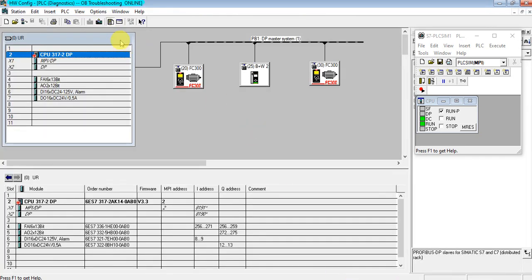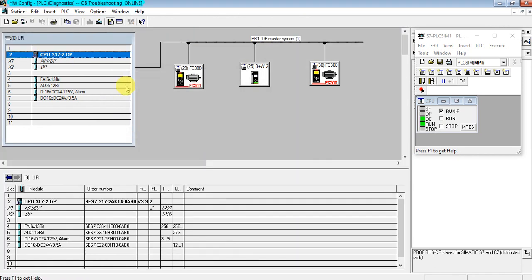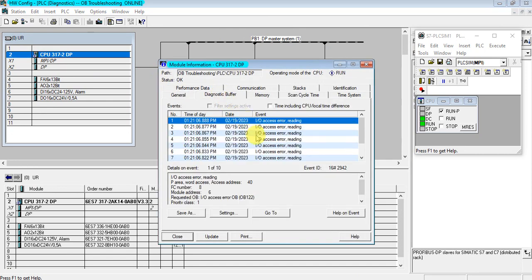Let's check the diagnostic buffer. On the diagnostic buffer, an IO access error shows. The access address is 40 and the function is 8. The module address is 6. We can extract these messages by using the default variables of OB122.